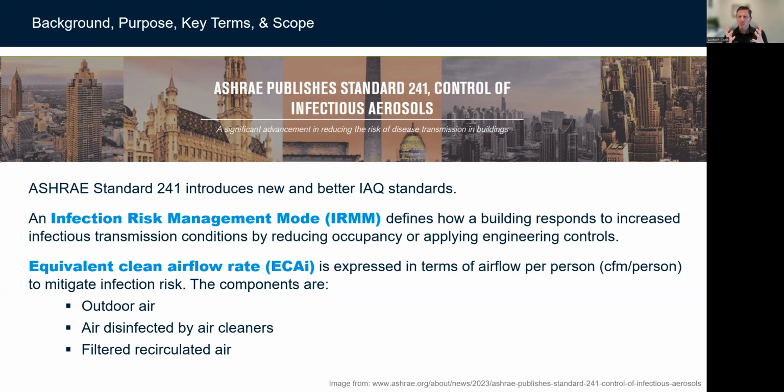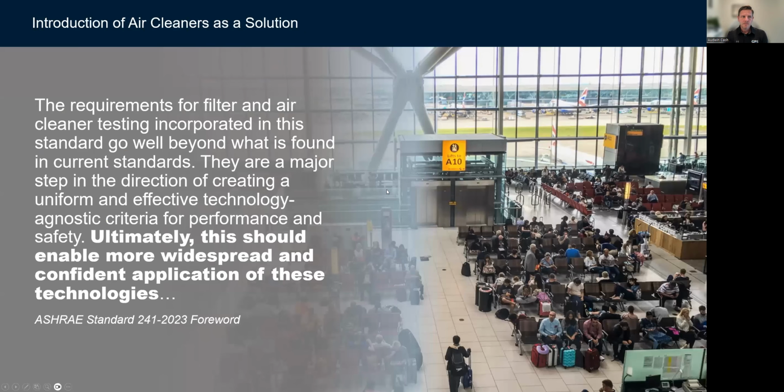Equivalent to what? In ASHRAE's terms, it's equivalent to bringing in outdoor air. Everything in this standard, outdoor air, air cleaned by an air cleaner, and filtered recirculated air, is equivalent when it comes to reducing the risk of infectious aerosol spread, which is pretty exciting. This is the first time there's really been an equivalency for these types of controls.